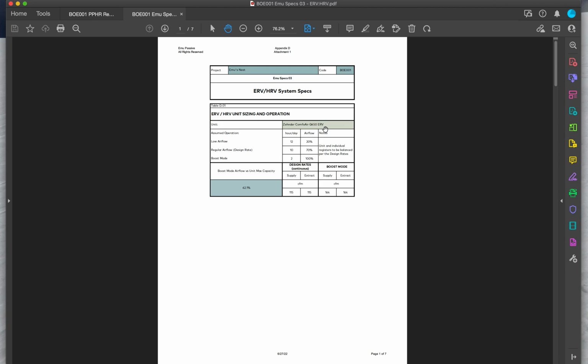ERVs are the ones that recover moisture as well as heat, and they work pretty well when the climate is very dry or very humid. So we typically spec ERVs in both very cold climates as well as really humid climates. Climate zones 6 and 7 typically spec ERVs. Climate zones 1 and 2, especially South Texas, Louisiana, Florida, all that nice, very humid climate, we end up specking ERVs. Anything in between, you can get HRVs, which recover heat, but they do not recover moisture.